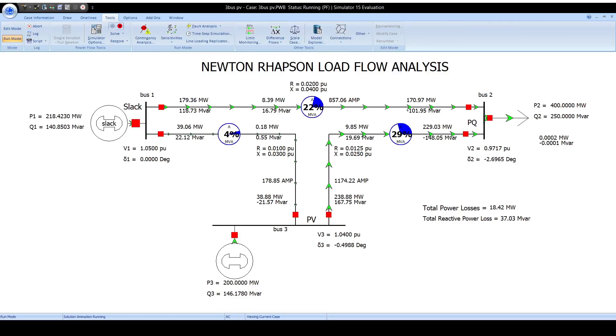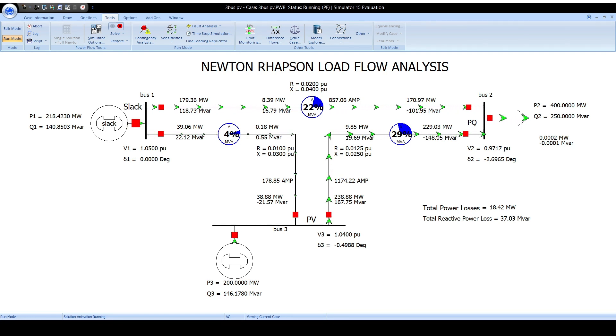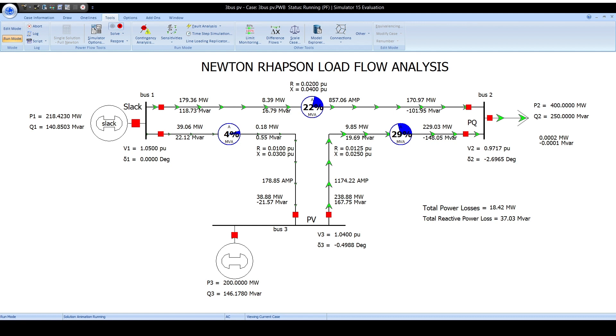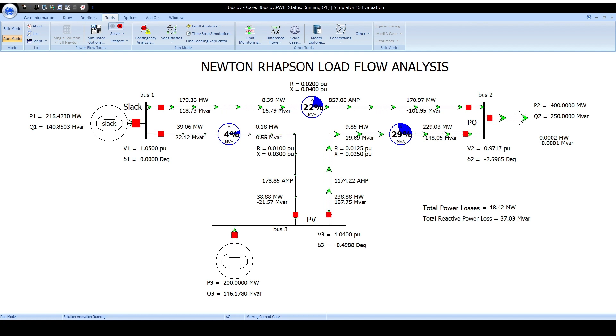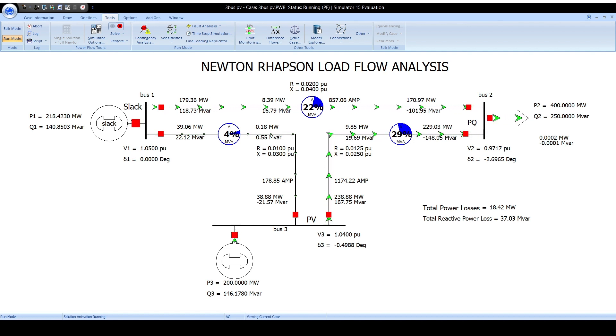This is load flow analysis using PowerWorld Simulator. We will find out how the solutions are obtained from this program. We will apply the Newton-Raphson method, which is a powerful method of solving nonlinear algebraic equations. Therefore, the convergence is very fast. The number of iterations is independent of the size of the system. Solutions to high accuracy are obtained nearly always in 2-3 iterations for both small and large systems.